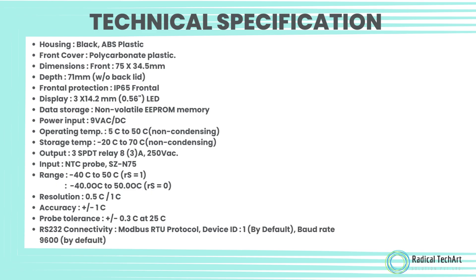Power input: nine voltage AC/DC. Operating temperature: 5 degrees Celsius to 50 degrees Celsius, non-condensing. Storage temperature: minus 20 degrees Celsius to 70 degrees Celsius, non-condensing. Output: three SPDT relay, 8 (3) ampere, 250 voltage AC. Input: NTC probe SZ-N75. Range: minus 40 degrees Celsius to 50 degrees Celsius, RS equals one; minus 40 degrees Celsius to 50 degrees Celsius, RS equals zero.